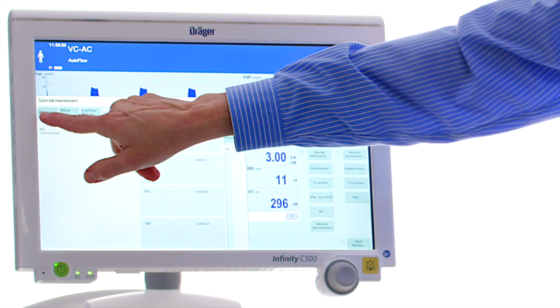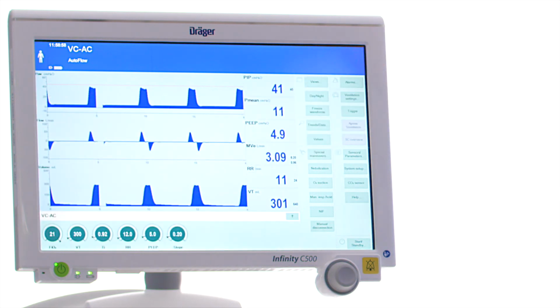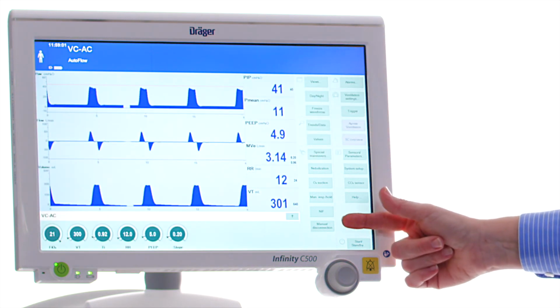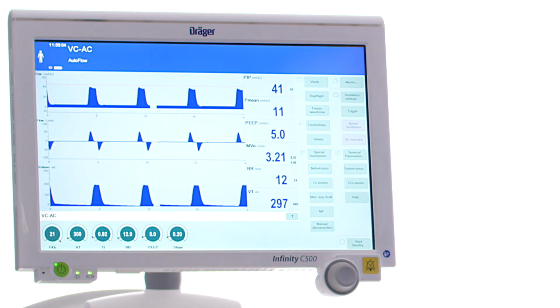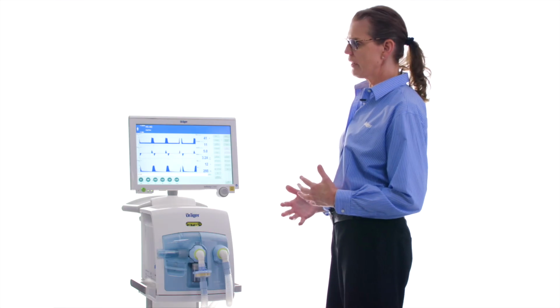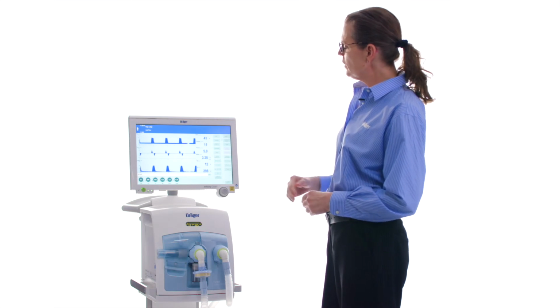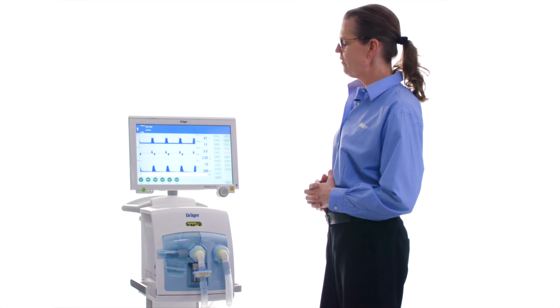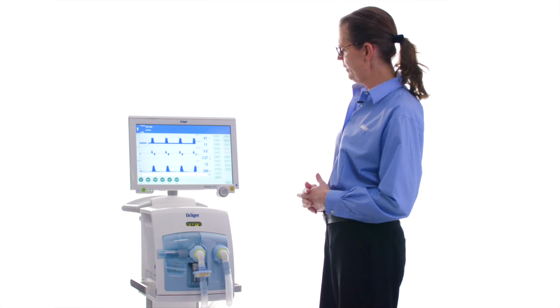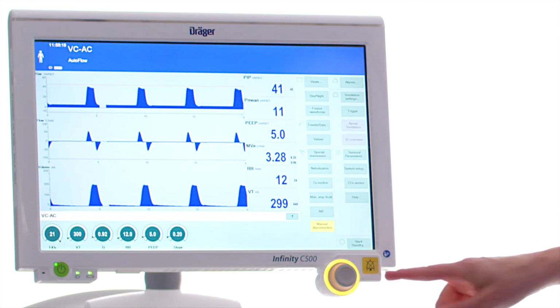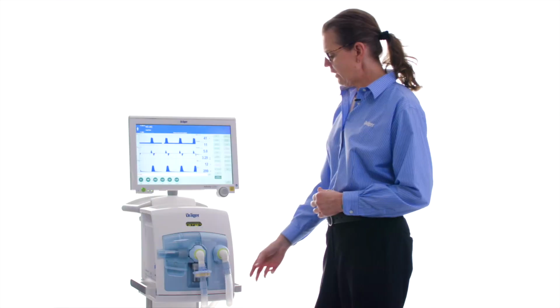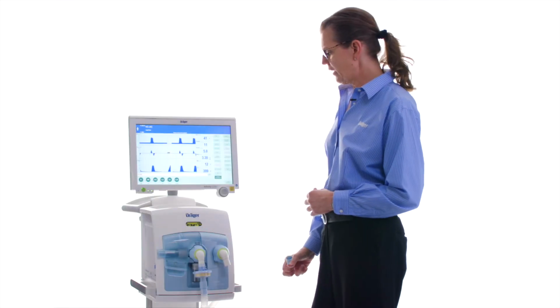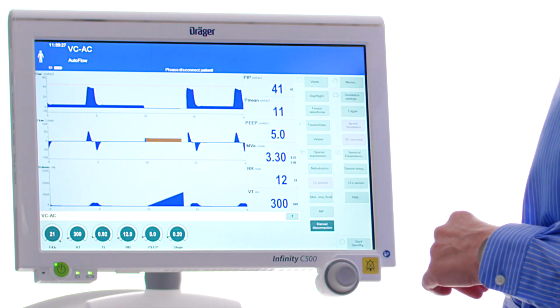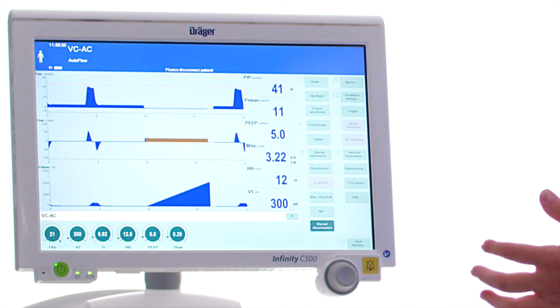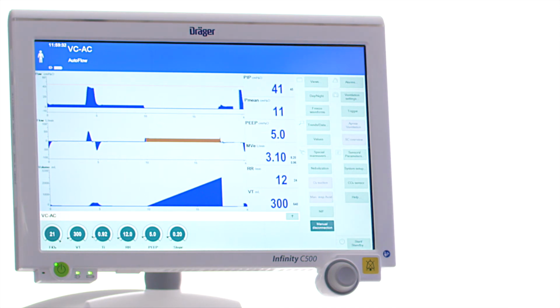If I go back to the main screen by touching the X, you're also going to see a button that says Manual Disconnect. This button is very important anytime we have to break the circuit in order to do any kind of function, so that we prevent contamination of the environment around the patient's bed. When you touch Manual Disconnect, it turns yellow and we confirm. It allows us to disconnect the ventilator circuit, provides a low flow state, does not spew gas around the room, and allows us to reconnect the patient as soon as we're done and go back to ventilating at the previous parameters.